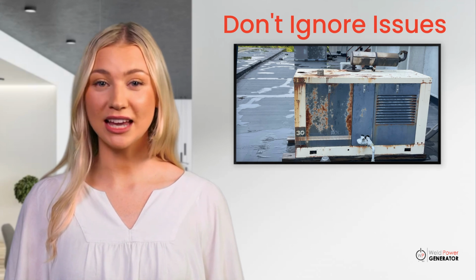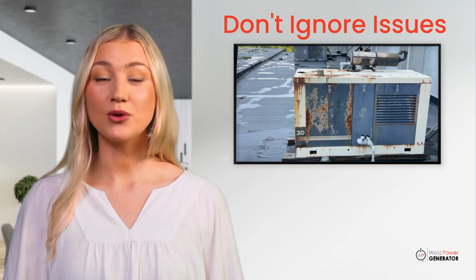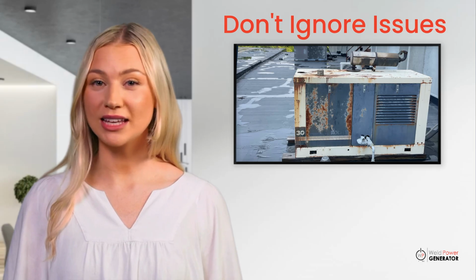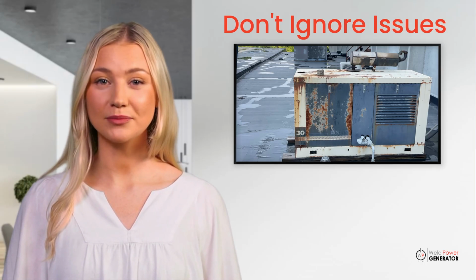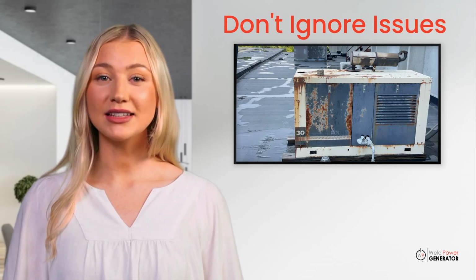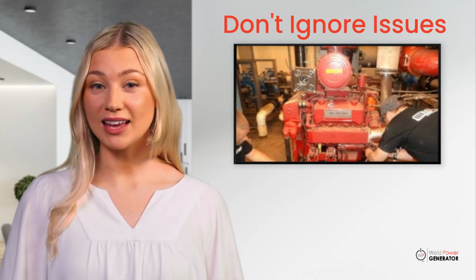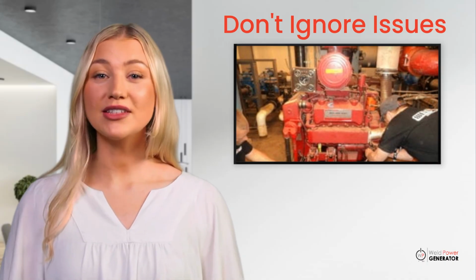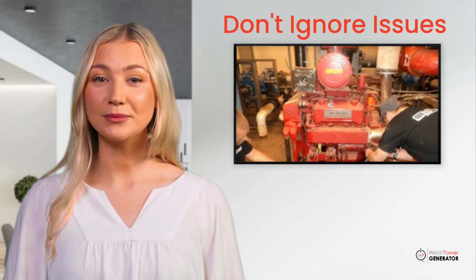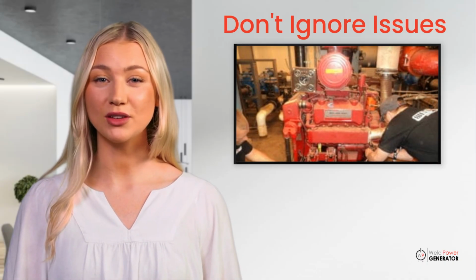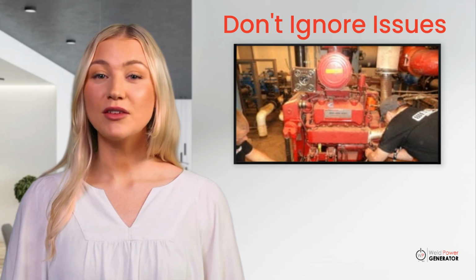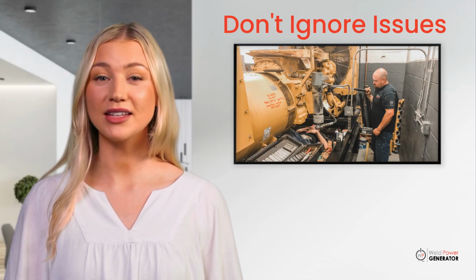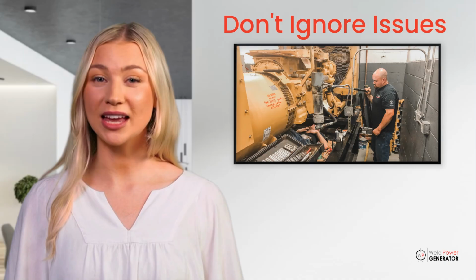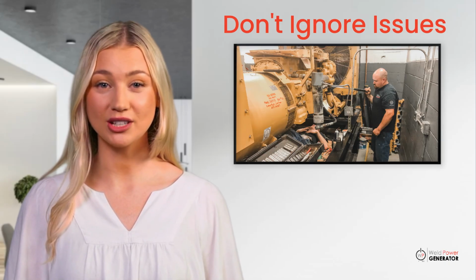A generator emitting unusual exhaust, running rough, or taking longer than normal to reach operating speed is telling you something. The instinct to defer investigation, especially when the unit is technically still running, is understandable but costly. Minor issues compound. A small coolant leak leads to overheating. An underperforming injector increases combustion stress on surrounding components. A battery that barely passes a load test will fail the next one, possibly during an actual emergency.